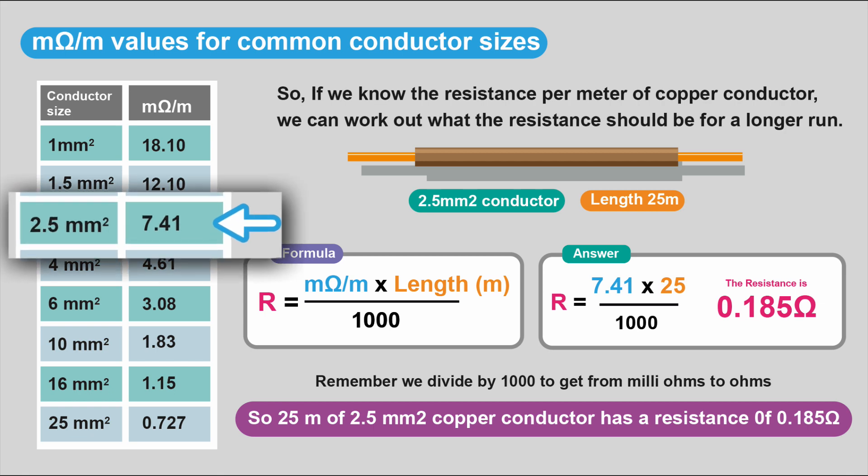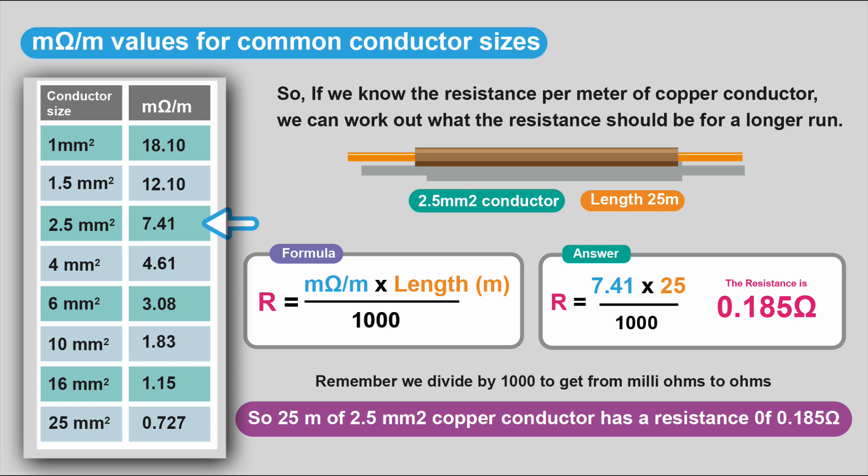Here we can see the 2.5 millimeters squared conductor, the 7.41 milli-ohms. There's publications that give this value for all the different cable sizes. Here I've just got from 1 millimeter squared to 25 millimeters squared, which are common cable sizes we use.